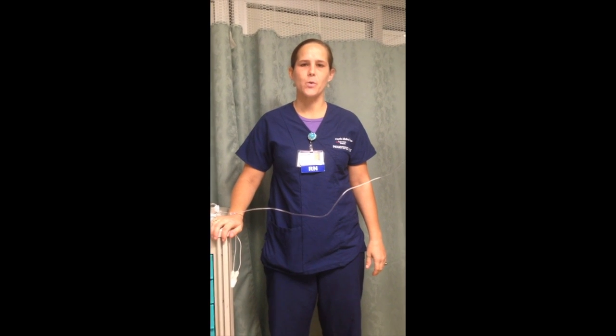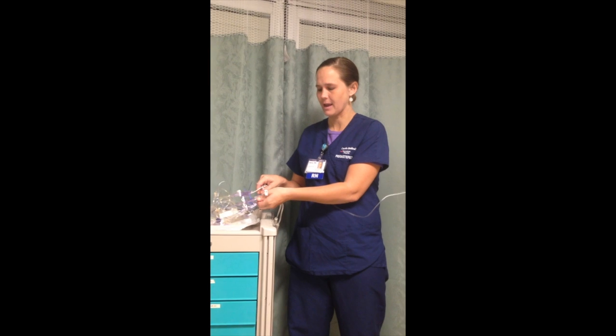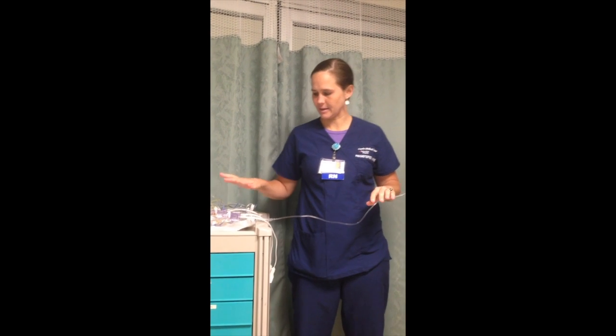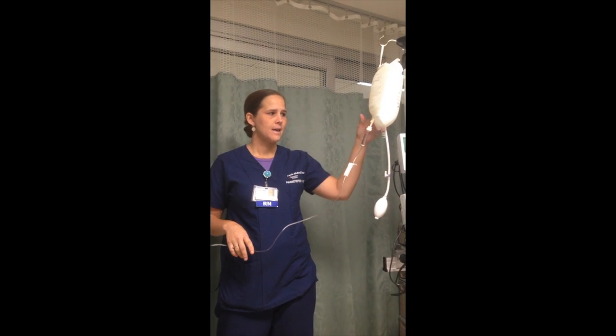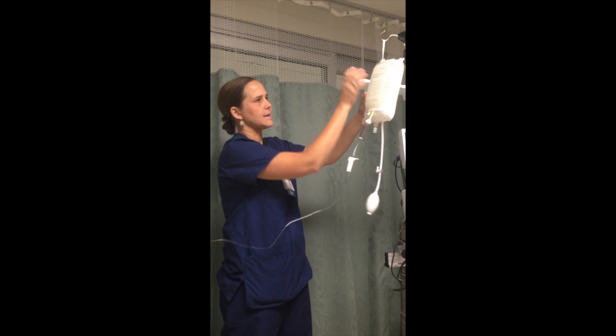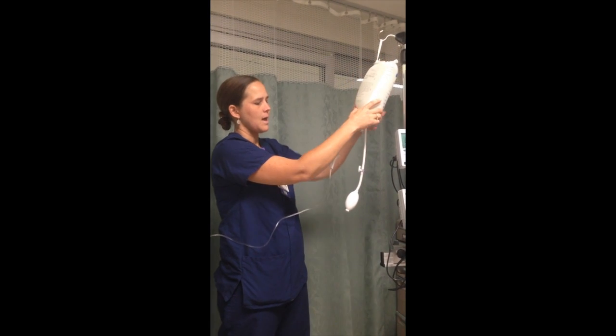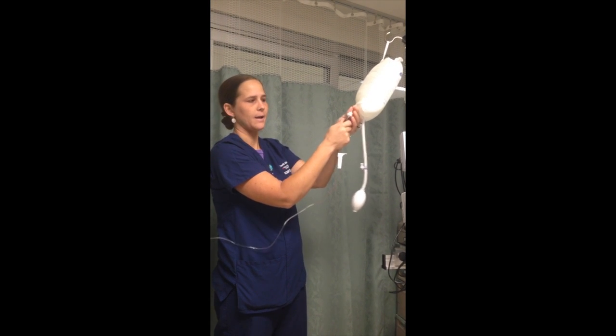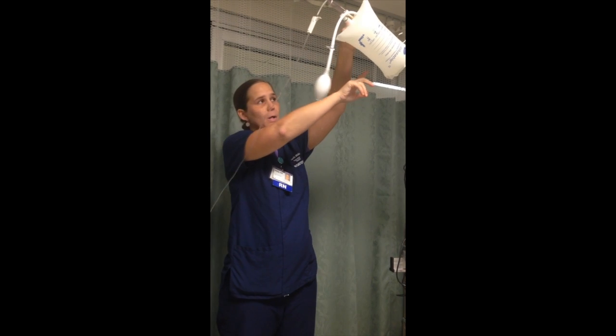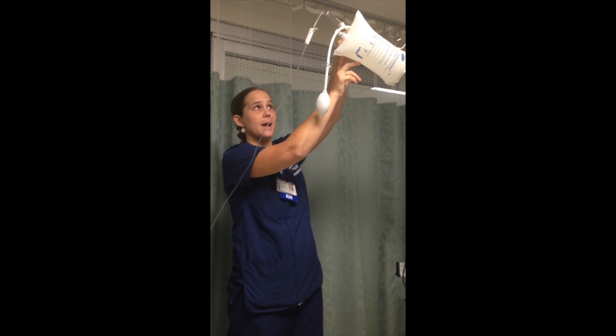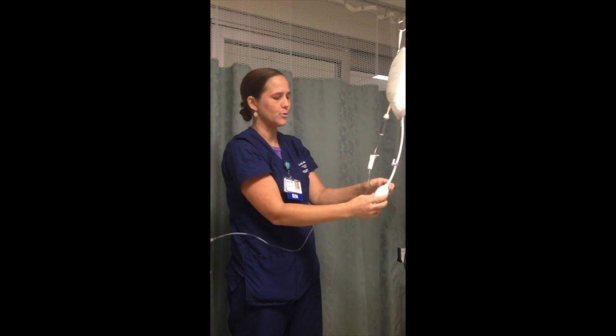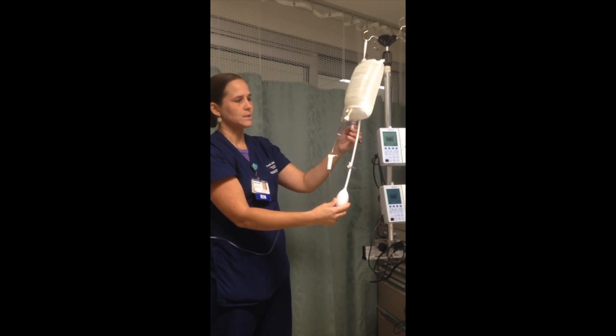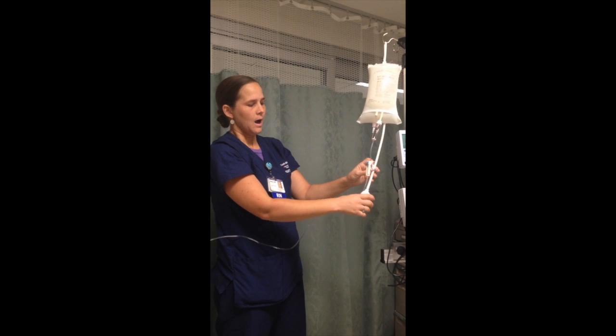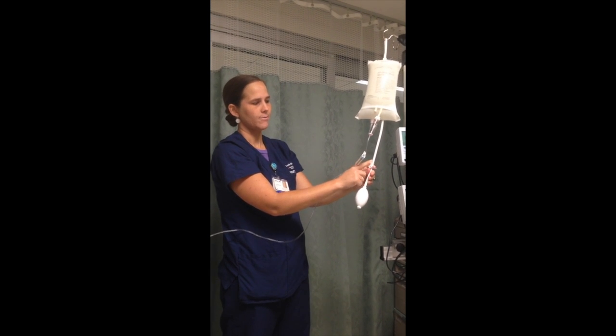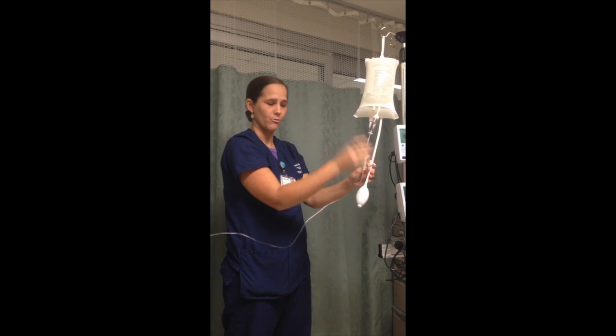This portion of the video will review how to set up the pressure tubing line. For the Swan Ganz, we're going to use the triple bifurcated pressure tubing. And to set it up, you will need the tubing, you'll need a 500cc bag of saline, and a pressure bag. You insert the saline into your pressure bag, clip it onto the little hook here, and before you inflate it, you spike the saline bag. At that point, you take the spike back out, invert it, and expel any air that's left inside the 500cc saline bag. You put the spike back in, and you inflate the pressure bag to the green level, which is 300 millimeters of pressure. After you inflate it, make sure you turn the stopcock off to the up position, otherwise the pressure bag may go flat.